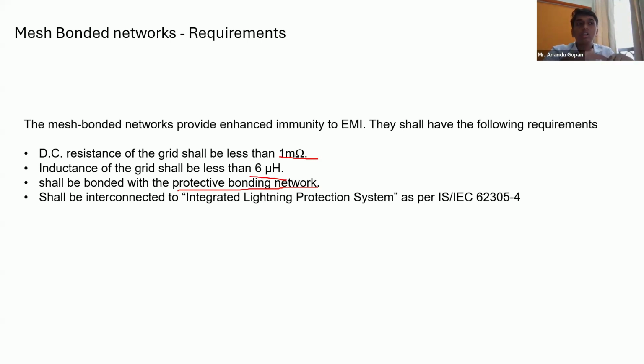Part 4 is for protection against these effects; this is for electronics and electrical equipment. If you want to protect your electronics and electrical equipment, you have to follow part 4 of IEC 62305. Part 4 is more stringent than part 3. You'll have a lot of design requirements such as shielding, bonding, SPD requirements, equipotentiality. Those requirements will be covered only in part 4.